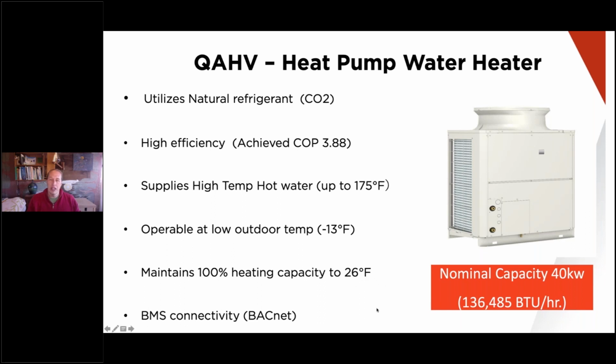So here is Mitsubishi's. It's a good product. I don't mean to call it dregs. I'm just saying they get better. This is not the highest efficiency available in Japan. So CO2, it has a 3.88 efficiency. In comparison, Sanden, that's a CO2 heat pump that's in the United States right now, that we've tested out as its boiler function at 4.5 on average over a year.